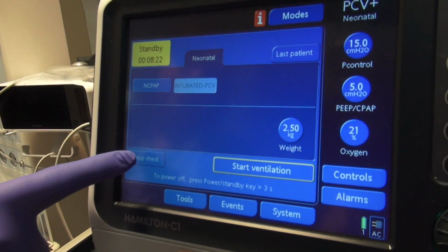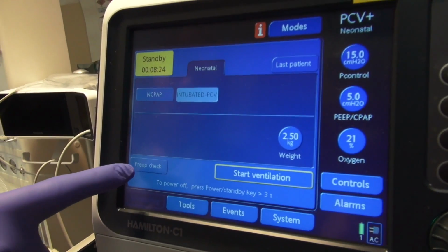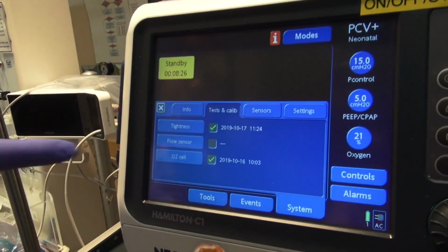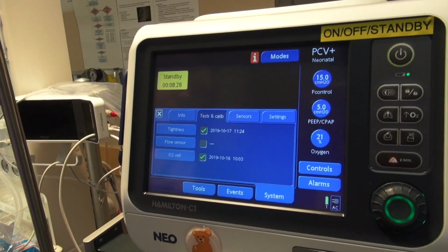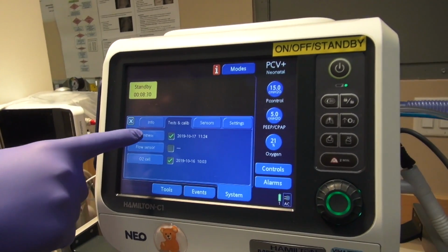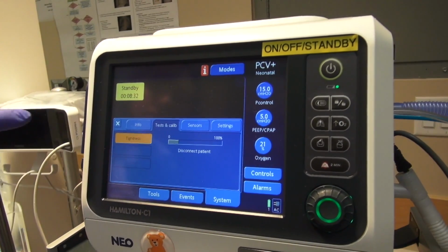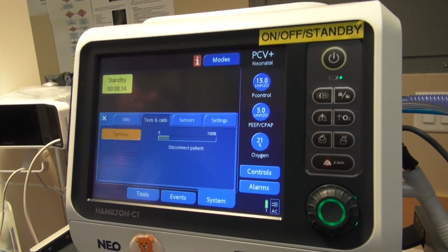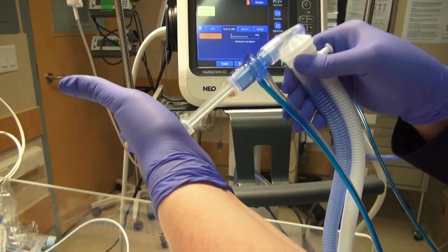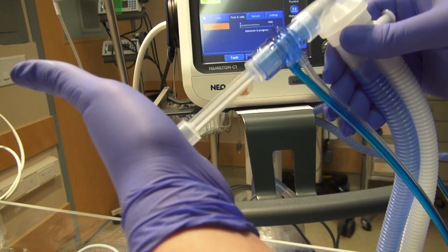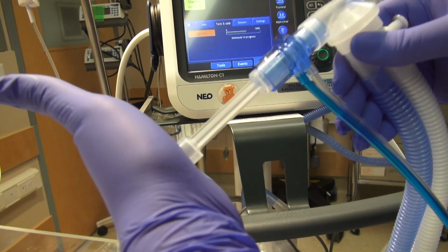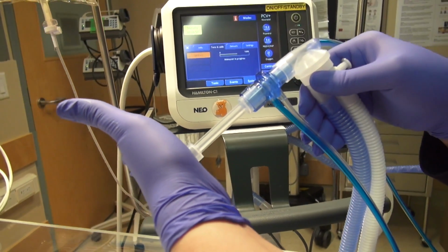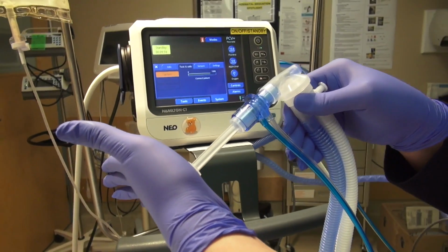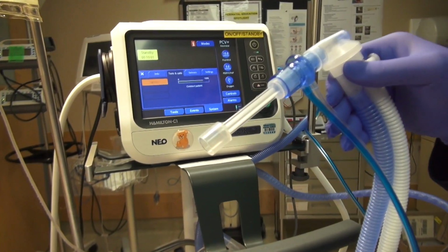Pre-op check for ventilator. Touch pre-op check button on the screen. Perform the tightness test. Follow the prompts and occlude end of system when it says tighten patient system. Wait for the green check. Once you get the green check, proceed to flow sensor check.